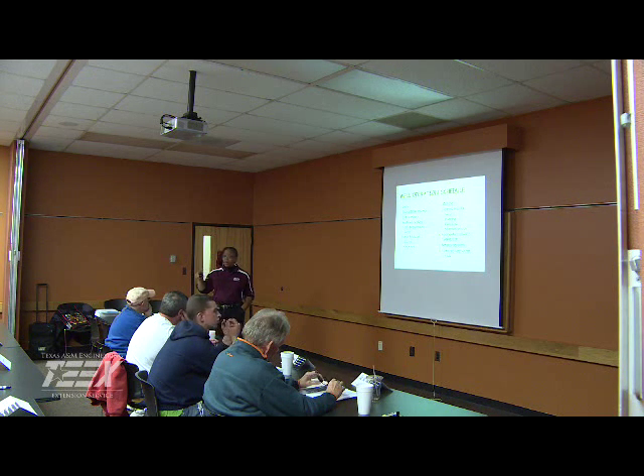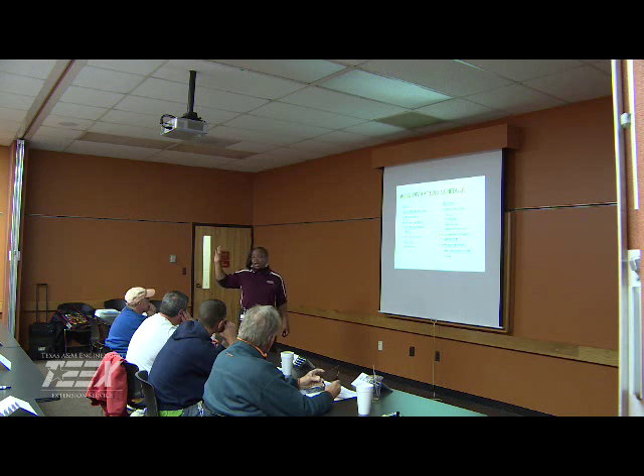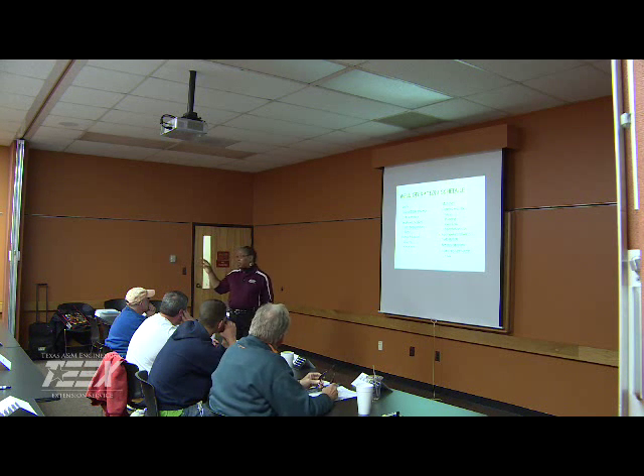Y'all familiar with that one? Okay, with the brake horsepower, and if I had a board, I could actually demonstrate, we're looking at the gallons per minute times your total head, divided by 3960, which is a constant for the foot-pounds per gallon of water. That's where 3960 comes from: 33,000 divided by 8.34, which is the weight of 1 gallon of water. And that will be divided by your pump efficiency.